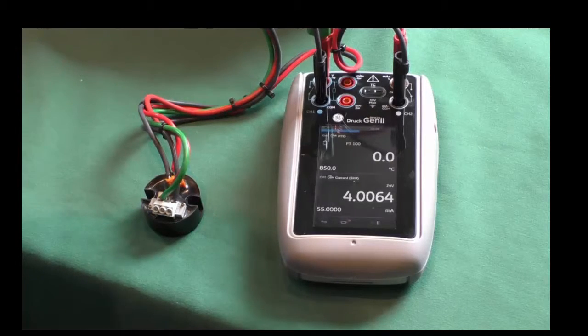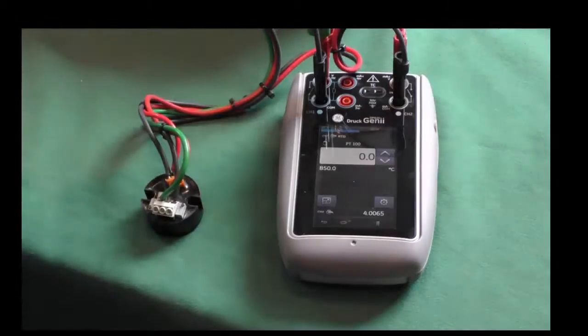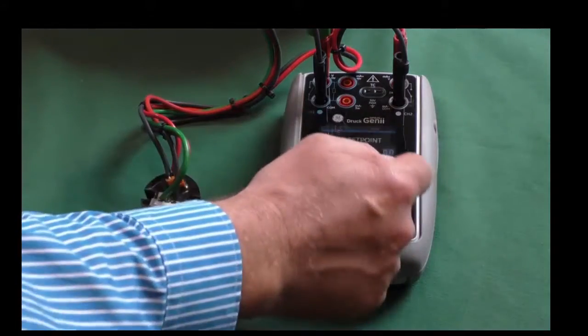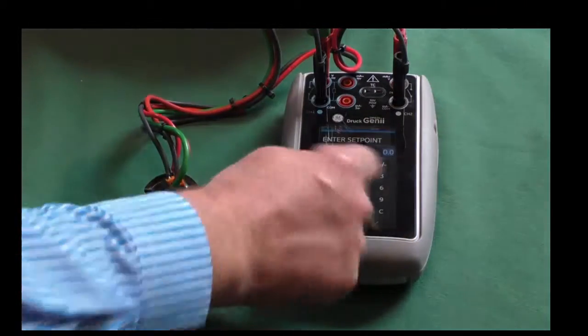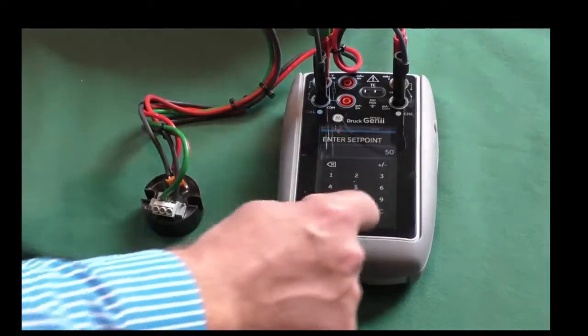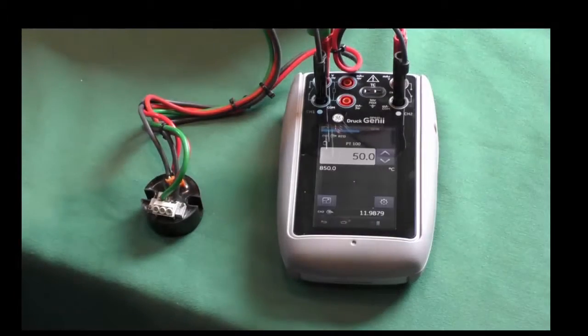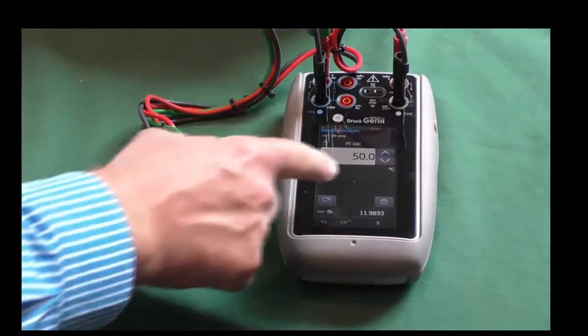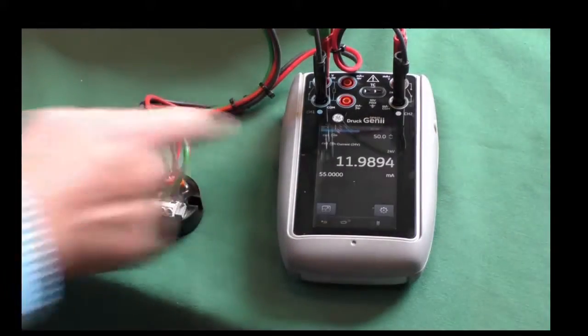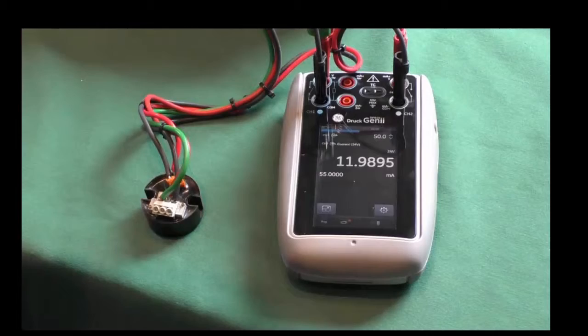We can simply go in and edit the value and type in what we need. If I want to go to 50 degrees C, I enter 50 and hit the tick button. We now have 50 degrees C. I press on the bottom channel, and you'll see there's nearly 12 milliamps, which is half of its range.